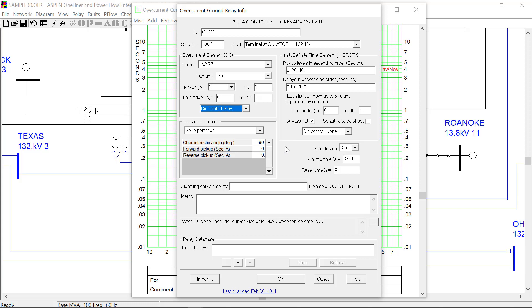The third set of new features I want to point out is some new settings in the directional element. For the voltage polarized element, you will have new settings for forward pickup and reverse pickup level.